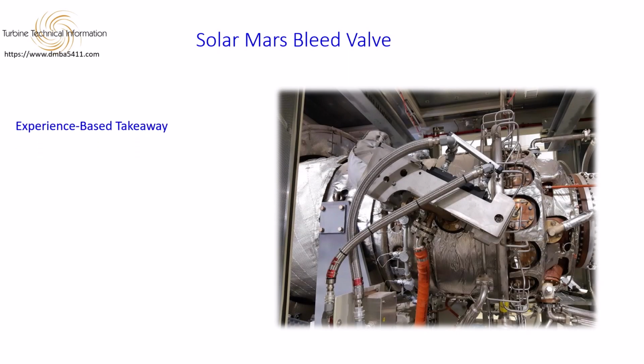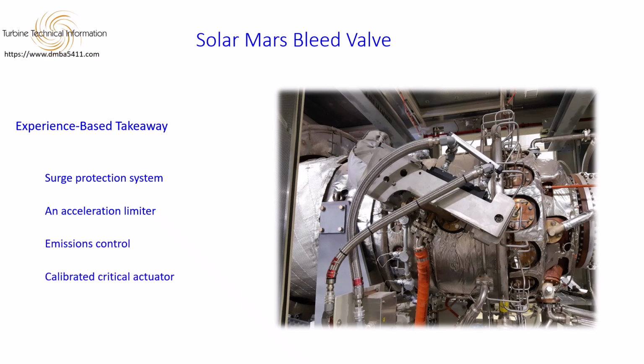Experience-based takeaway. The Mars bleed valve is not just a start device. It is a surge protection system. An acceleration limiter. Part of emissions control. A calibrated critical actuator. Get it right, the machine starts clean and smooth. Get it wrong, and the symptoms will send you everywhere, except to the real issue. And that's why experienced technicians look at the bleed schedule early in a startup problem.